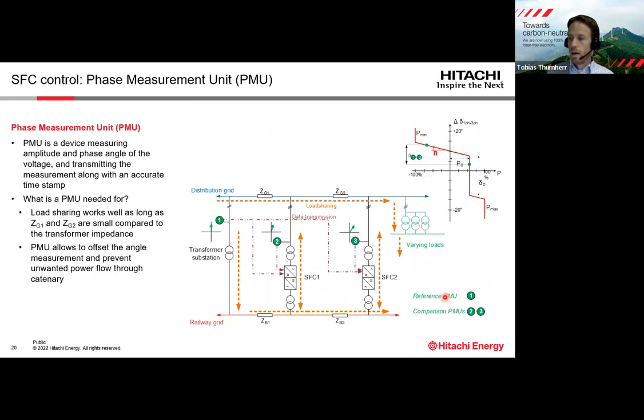Also in the Potteric Carr project, a phase measurement unit, a so-called PMU, was specified and is implemented. A PMU is a device that measures the amplitude and the phase angle of the voltage where it is connected, and it then transmits these measurements along with a very accurate timestamp of the measurement. There are different possibilities to use this PMU, but I would like to show just one example of how it can be used.